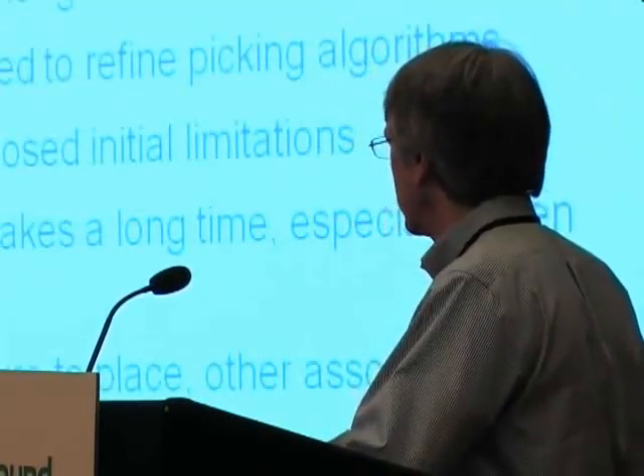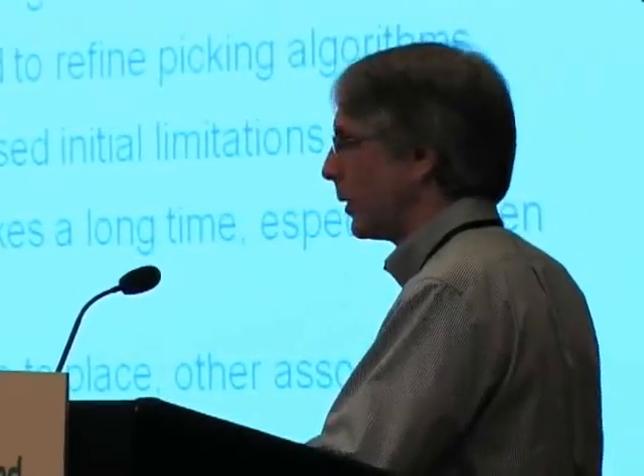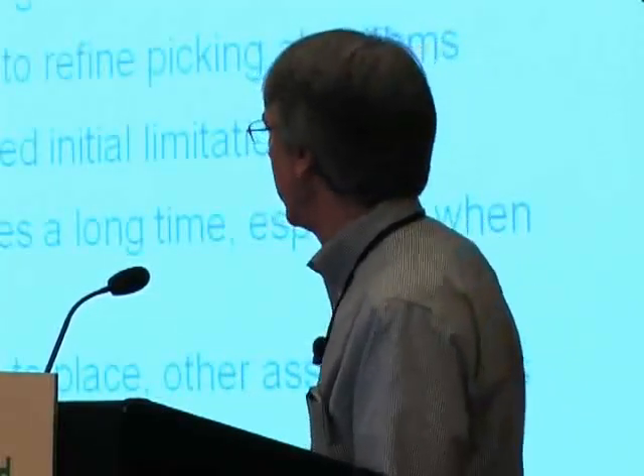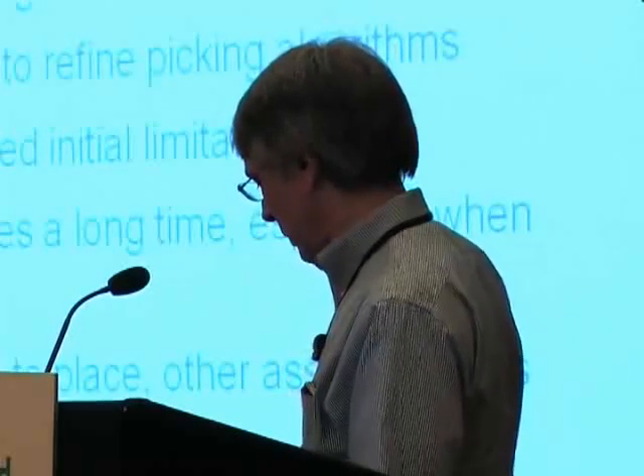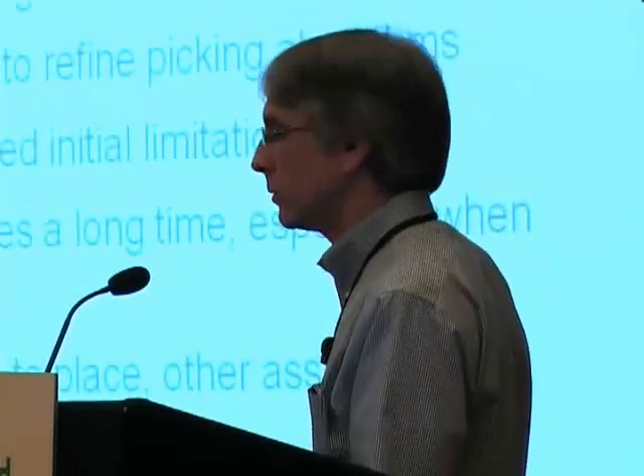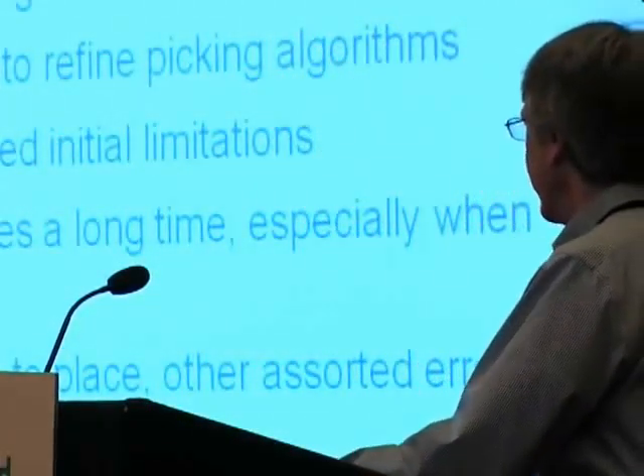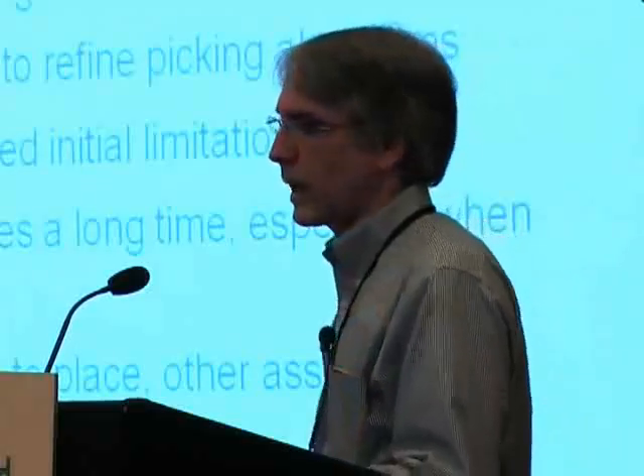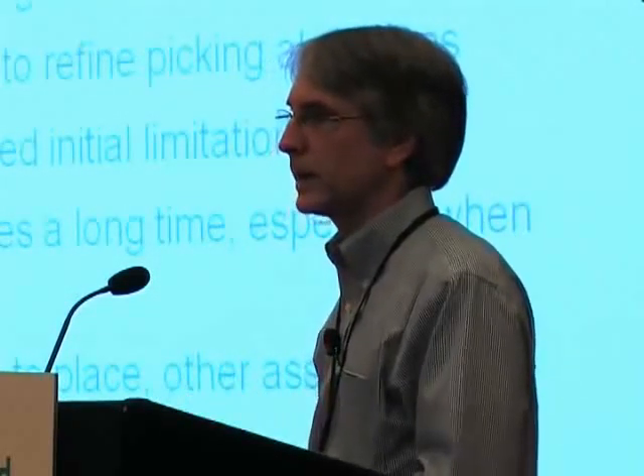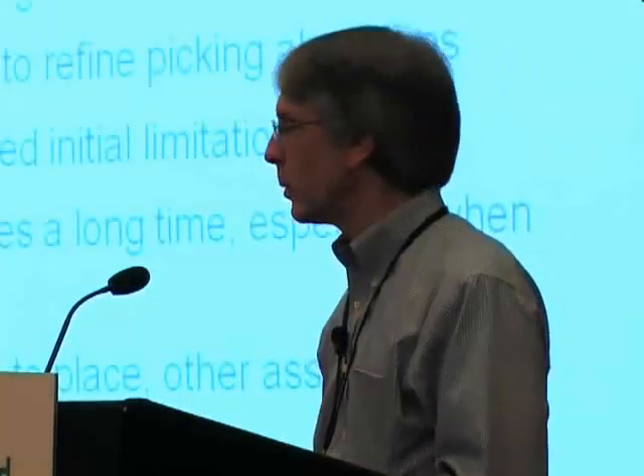We had some problems with tubes dropping or not being picked properly, not being placed properly, or errors like that. These are all the growing pains of working with a new technology, a new system. I think most of that now has been pretty much resolved and under control, but it presented challenges and delayed our implementation. And then the final problem: integration with the compound management software. There's always things you didn't expect, always things that came up at the last minute that kind of throw a wrench into the works that we had to deal with.